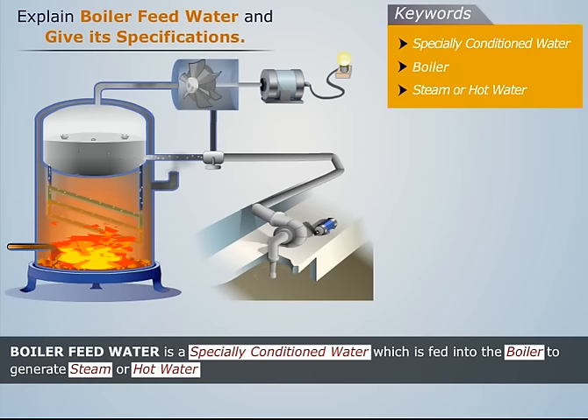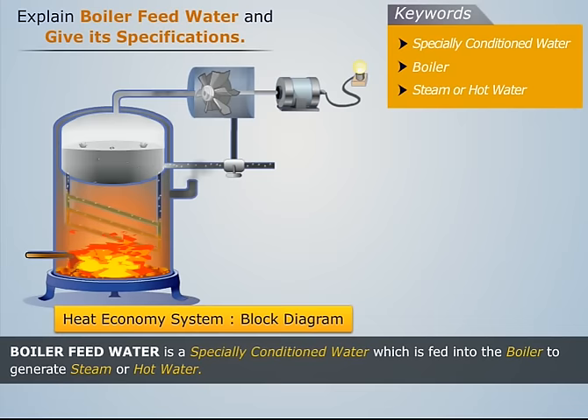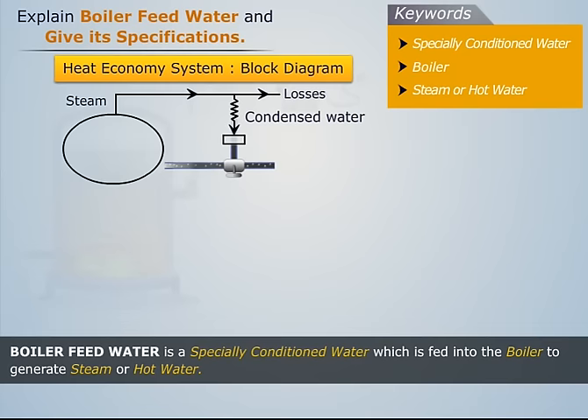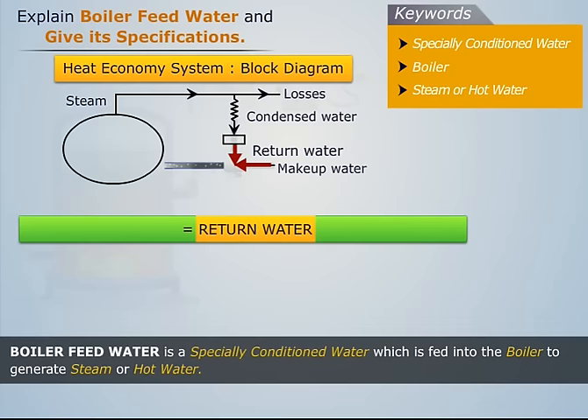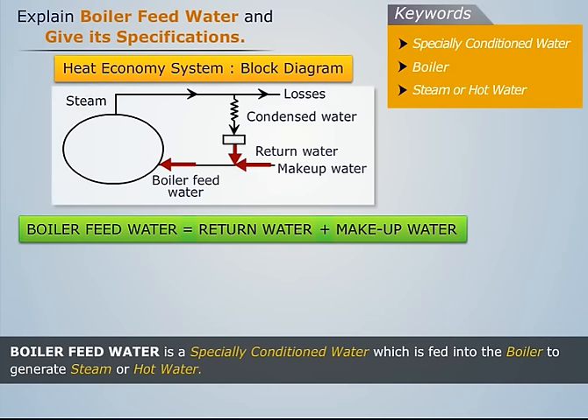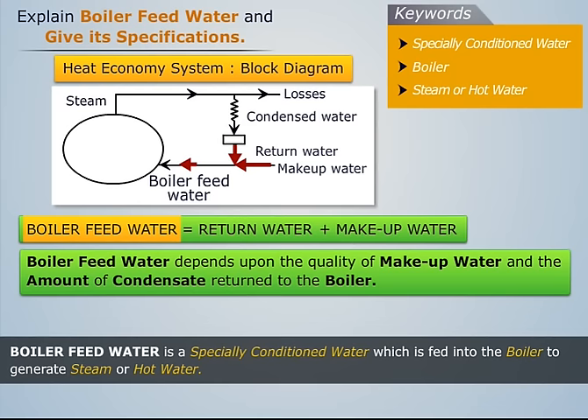Boiler feed water is generated through a system of heat economy. Steam produced in the boiler is condensed after use and returned as pure feed water, called the return water. Some fresh water, or makeup water, is then added to this return water. It is this combination of return water and makeup water which is fed into the boiler as the boiler feed water to generate steam. Note that boiler feed water quality depends upon the quality of the makeup water and the amount of condensate returned to the boiler.